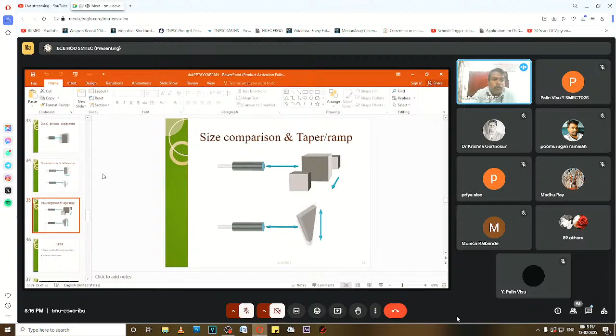The main inductive sensor we are well versed in is the Linear Variable Differential Transformer, or LVDT. The LVDT has a single primary coil and two secondary coils. The primary is supplied with AC, and the two secondaries link with the flux. The metal object is in the form of a core, which moves in between the primary and secondary coils.